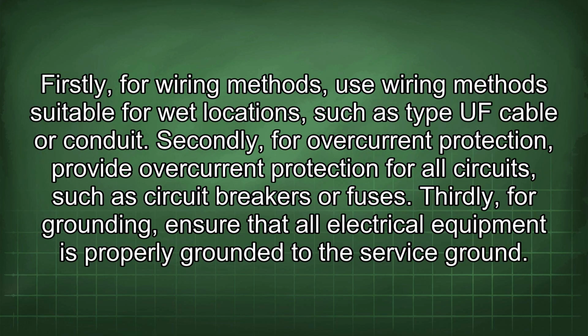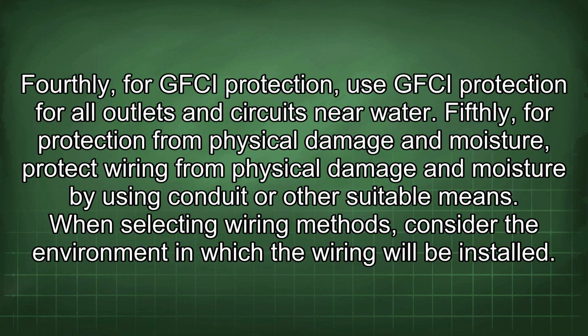Firstly, for wiring methods, use wiring methods suitable for wet locations such as type UF cable or conduit. Secondly, for overcurrent protection, provide overcurrent protection for all circuits, such as circuit breakers or fuses. Thirdly, for grounding, ensure that all electrical equipment is properly grounded to the service ground. Fourthly, for GFCI protection, use GFCI protection for all outlets and circuits near water.